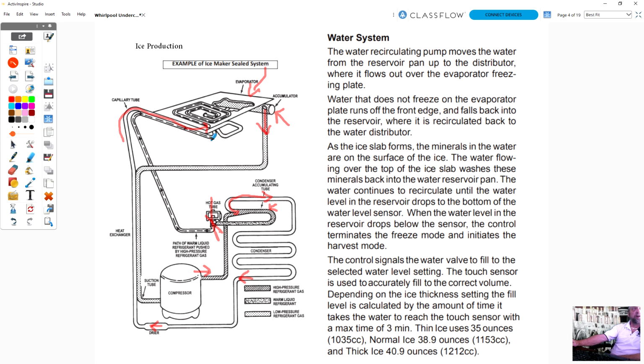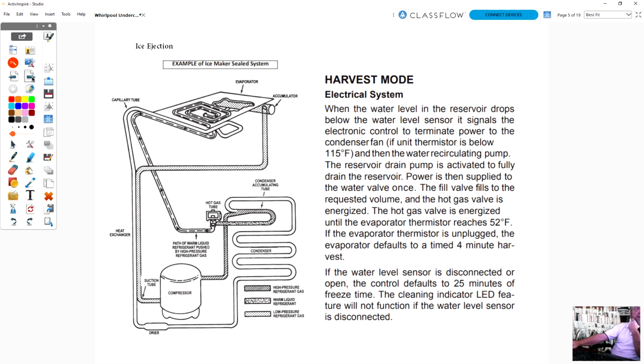as we go through the manual as far as how that works, because the cycle of the older ones versus the newer ones, initiating that cycle has now been done a little differently. So in the harvest mode, this is where we're going to have some changes. There is a water level sensor in the reservoir that the machine fills up to circulate over the unit. And I'll show you pictures of that as we go through. The older ice makers, the original design that they made, didn't have anything that controlled the water inside the recirculation container there. It would just fill up, and anything over the amount would run through an overflow and just run right out the drain.